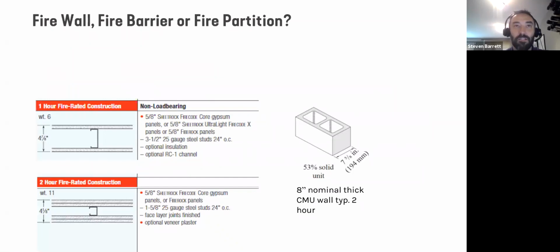So just a little pop quiz. We actually have a poll question for this. You see here on the screen, I've got 1 hour fire rated construction. That's 5/8 inch gyp on either side of a metal stud. That's a 1 hour rated assembly. Below that is 2 5/8 sheets on either side of the stud. That's a 2 hour configuration. And then CMU block, that's 8 inch nominal thick, is typically also 2 hours. So my question for you all, is this a firewall, a fire barrier, or a fire partition?